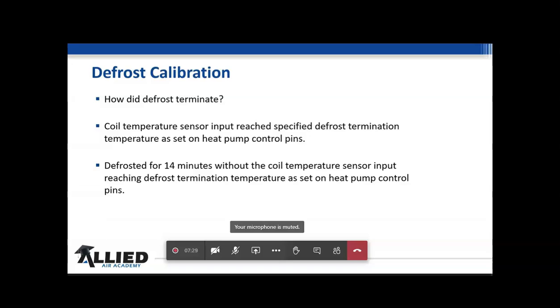Defrost for 14 minutes without the coil temperature sensor input reaching defrost termination temperature as set on the heat pump control pins. Now, if we're in a very cold climate and it's a cold day when they put this in and it has to run 14 minutes, it's going to calibrate to that. And a lot of folks get worried, okay, what's going to happen when it warms up? It calibrated when it was real cold, and when it warms up, what's it going to do? That's what I want to talk to you about. That's what I want to really get clear in everybody's head today on this.